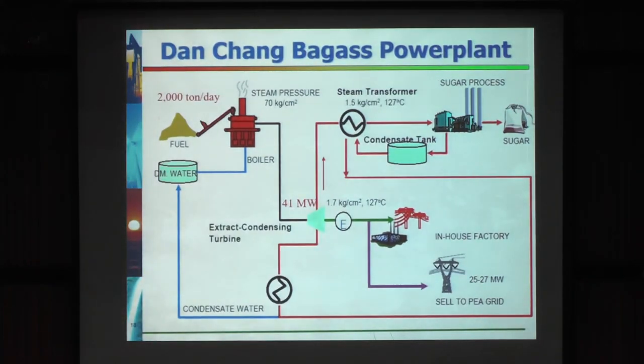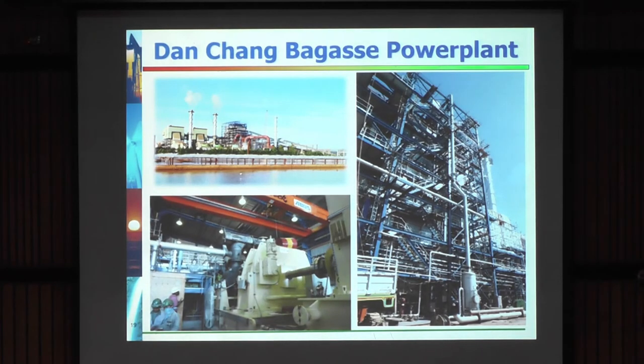Another example is the bagasse power plant. This plant can produce electrical power of up to 41 megawatts. And for 41 megawatts, we need to feed bagasse at more than 2,000 tons per day. We use a different boiler and produce steam up to 70 bar. This is a cogeneration power plant, in which from one combustion we get steam, use the steam to produce electrical power, and some of the steam is used to feed the process of the plant. So we call it a cogeneration power plant. This is the picture of this 41 megawatt power plant. It's a big power plant and uses very sophisticated machines and equipment.